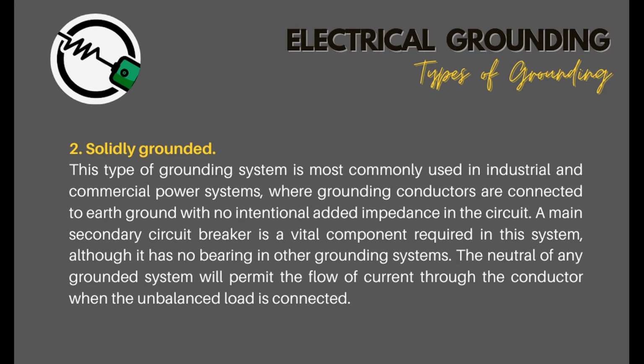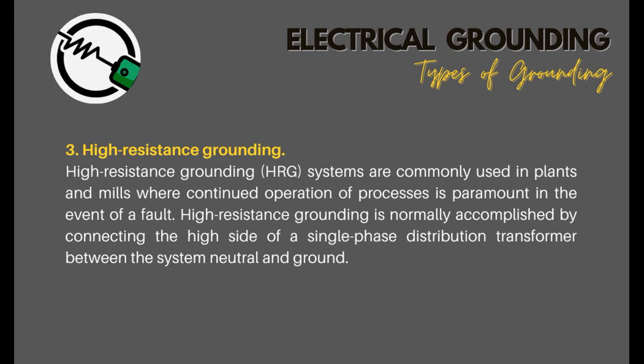2. Solidly grounded. This type of grounding system is most commonly used in industrial and commercial power systems, where grounding conductors are connected to earth ground with no intentional added impedance in the circuit. A main secondary circuit breaker is a vital component required in this system, although it has no bearing in other grounding systems. The neutral of any grounded system will permit the flow of current through the conductor when the unbalanced load is connected. 3. High resistance grounding.